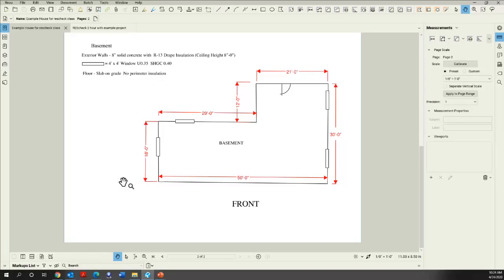64 square feet of window, and they're saying that it's a 0.35 U value with a solar heat gain coefficient of 0.4. Okay. We have a door, and it's got no dimensions on it. Well, we're going to make the grand assumption it's a 3068, and we're going to call that 21 square feet. Close enough. And we're going to say it's a glass door, more than 50% glass, so it's going to have to be the same as the windows: a 0.35 with a 0.40 solar heat gain coefficient.